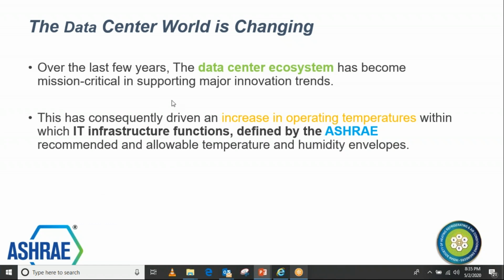In most of the data centers across India which we have seen, outside air is not used. Indirect cooling is used, with two coils: one coil connected to a cooling tower, one connected to the chiller, and the first coil pre-cools the hot air which is coming to the room. So these kinds of approaches are being used. Till now, direct air is used only in one of the data centers in Bangalore. They have used pre-filters up to MERV 13, and this is the only location across India which I find, in bigger data centers. So only these are the few questions which I could see quickly.